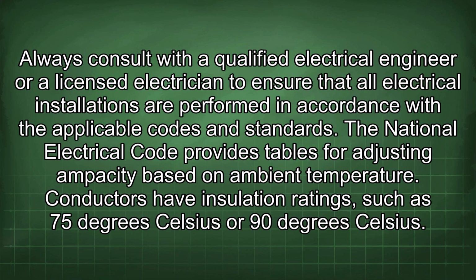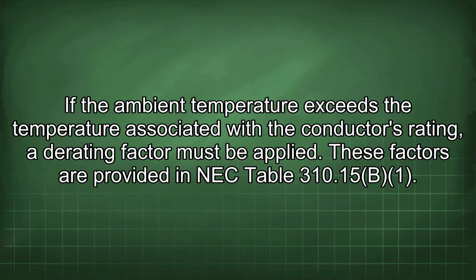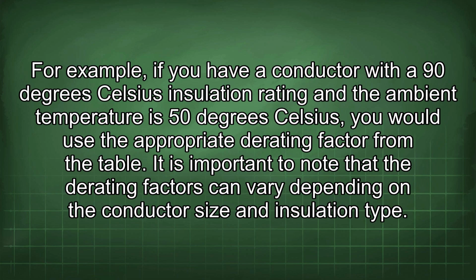The National Electrical Code provides tables for adjusting ampacity based on ambient temperature. Conductors have insulation ratings, such as 75 degrees Celsius or 90 degrees Celsius. If the ambient temperature exceeds the temperature associated with the conductor's rating, a derating factor must be applied. These factors are provided in NEC Table 310.15(B)(2)(a). For example, if you have a conductor with a 90 degrees Celsius insulation rating and the ambient temperature is 50 degrees Celsius, you would use the appropriate derating factor from the table. It is important to note that the derating factors can vary depending on the conductor size and insulation type.